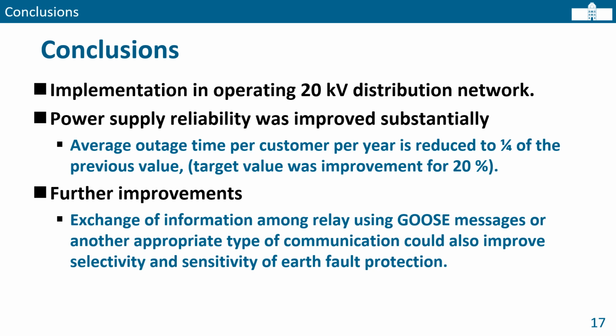Conclusion. The closed loop operation was implemented in the 20 kV distribution network. Power supply reliability was improved substantially. The target value was 20%. Based on the presented results, the outage time per customer per year was reduced to 1/4 of the previous value.